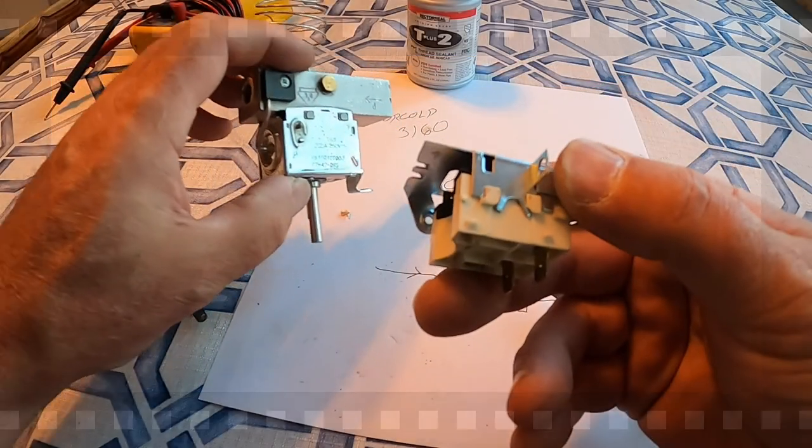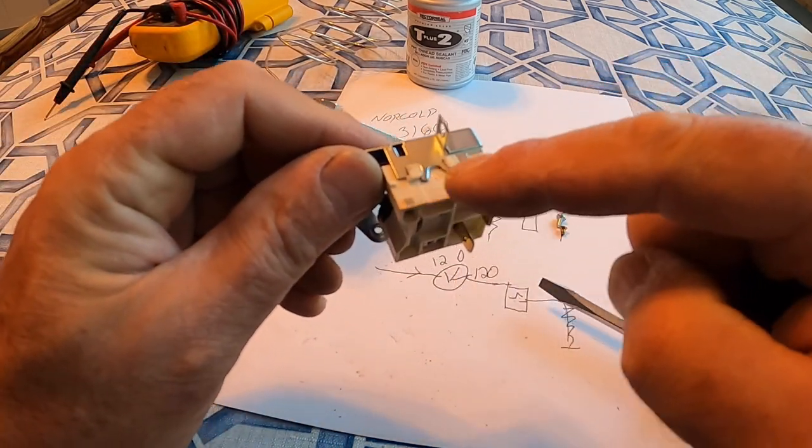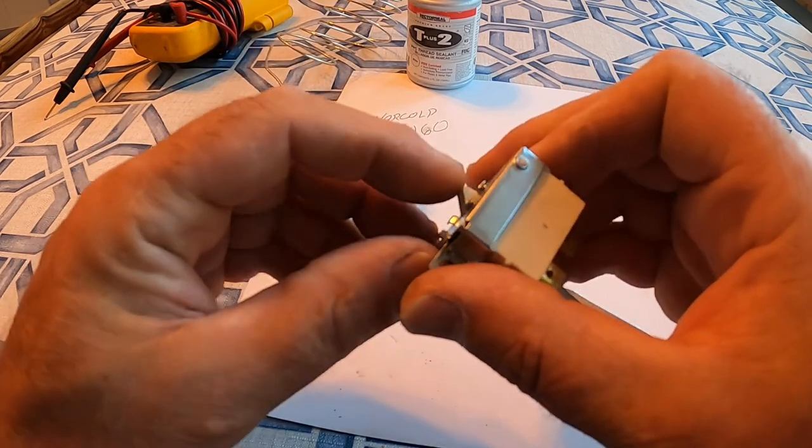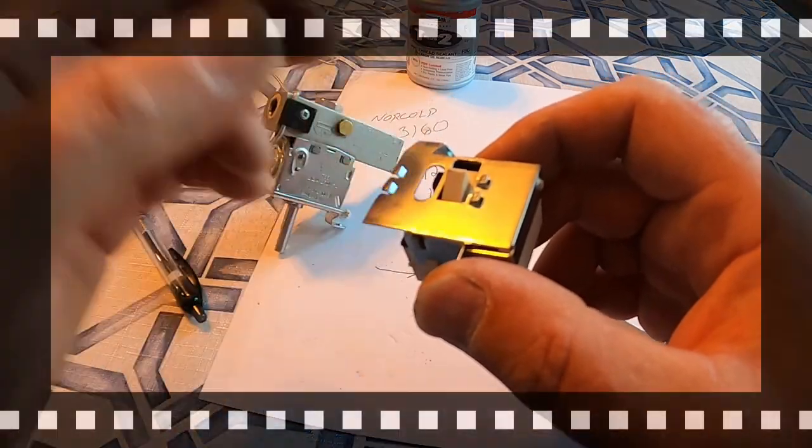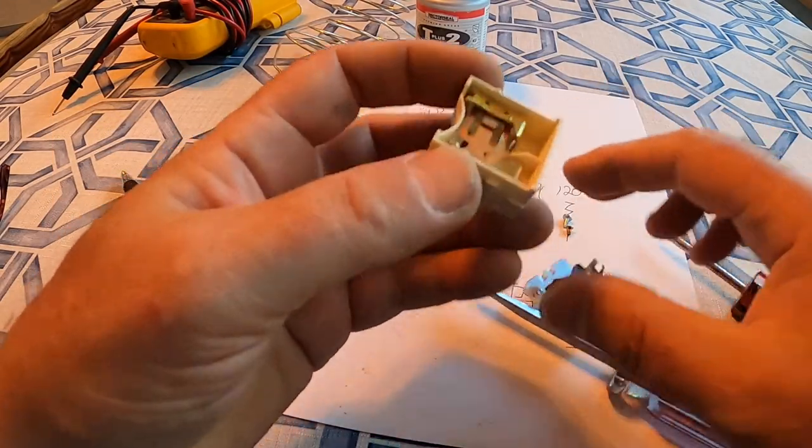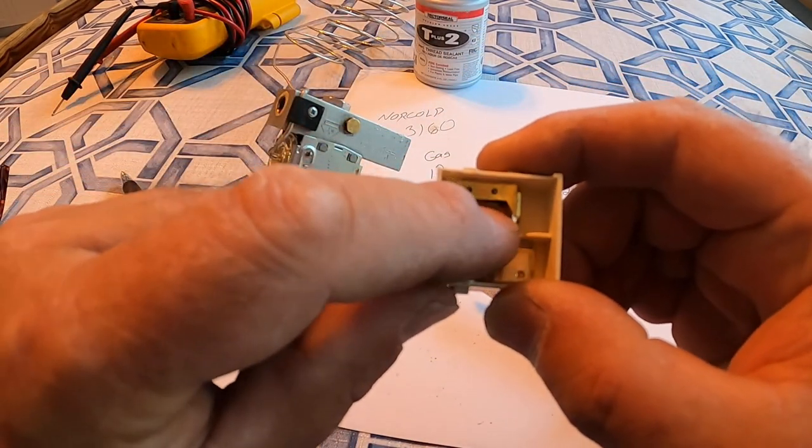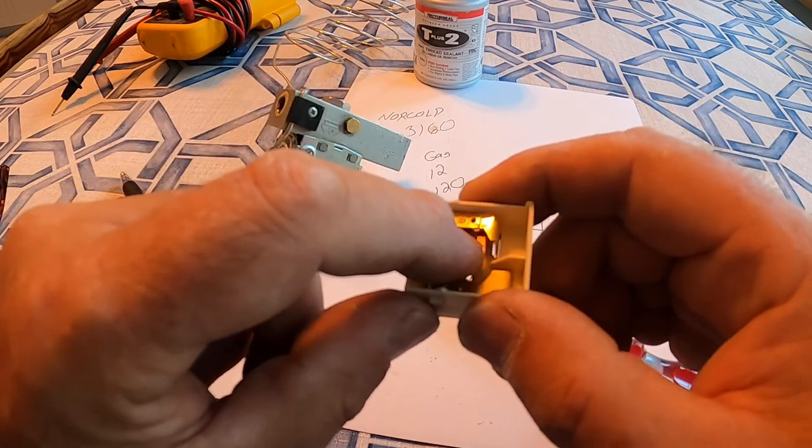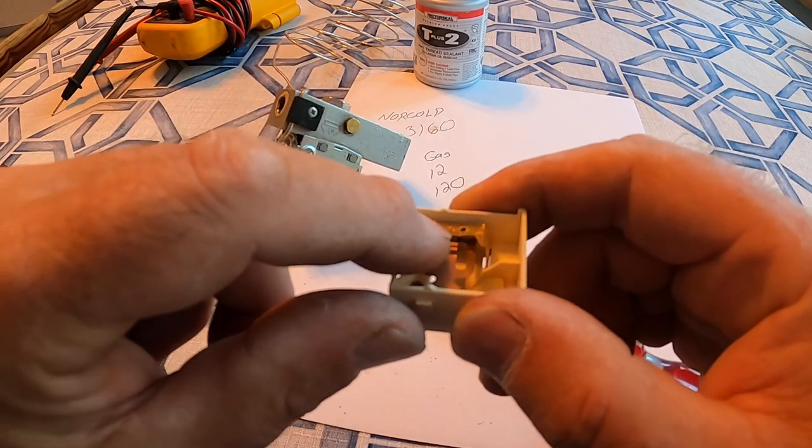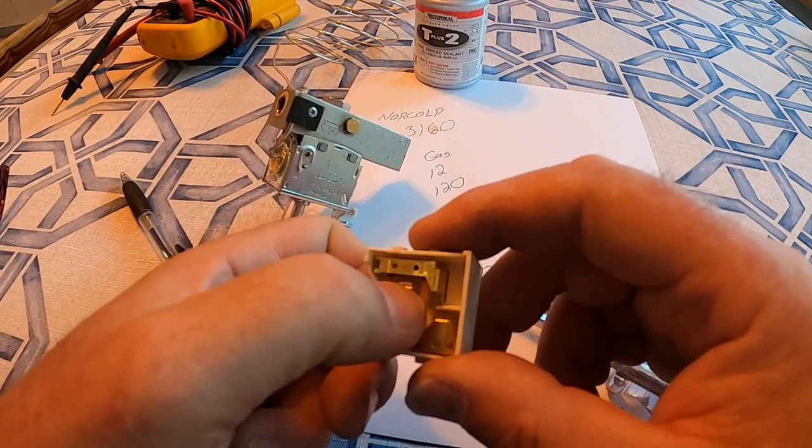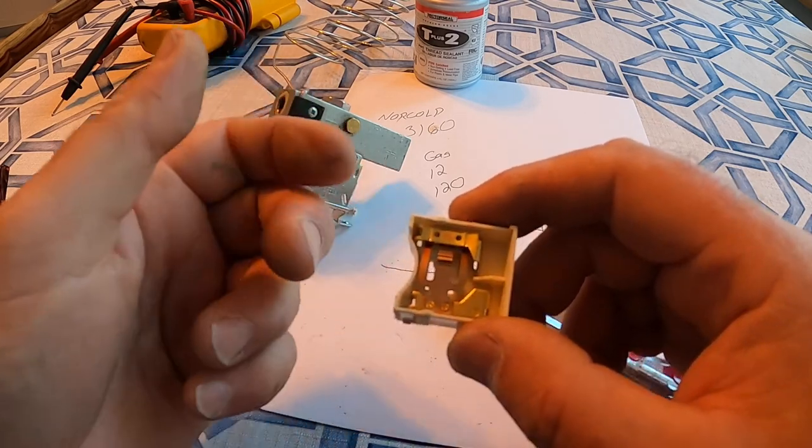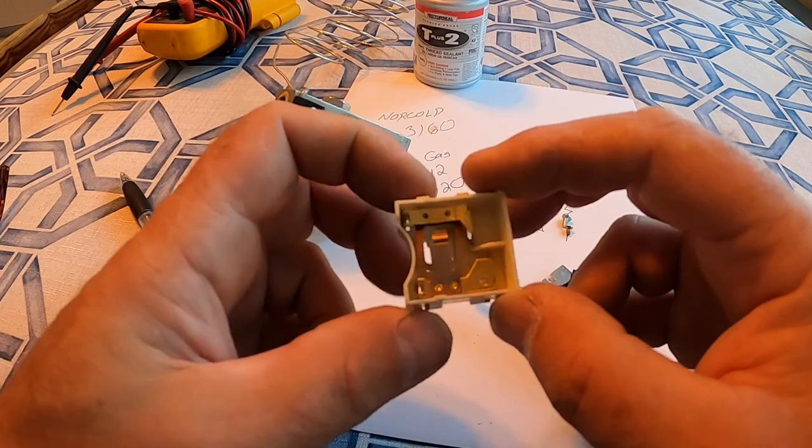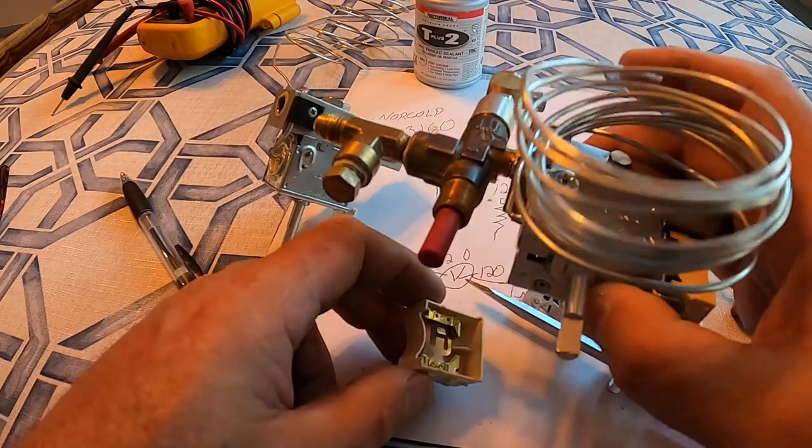Okay. We have that switch assembly off the gas valve assembly. We're going to go ahead and take these clips off. You can see this is just a switch. I want to get in there and find out what's going on with it. Okay. Here we've got the top assembly off and little contacts in here. It's too small to see. I don't have a macro lens here, but when I take a magnifying glass and I look in there, those little contacts are pitted and just worn out. Just like any switch gets after a hundred thousand cycles or so. Anyway, that was just informational. And we'll head out to the trailer and put this guy back in.